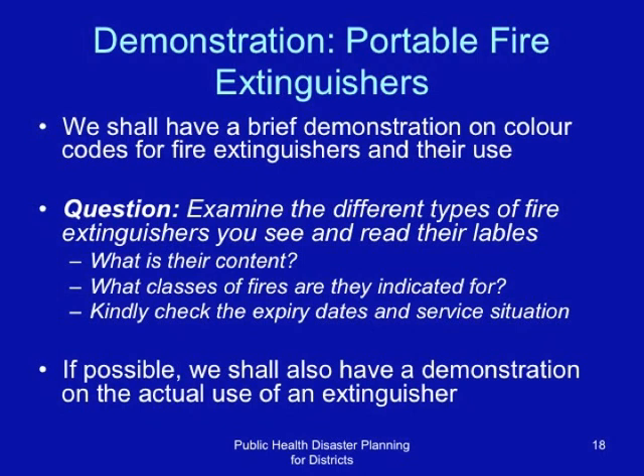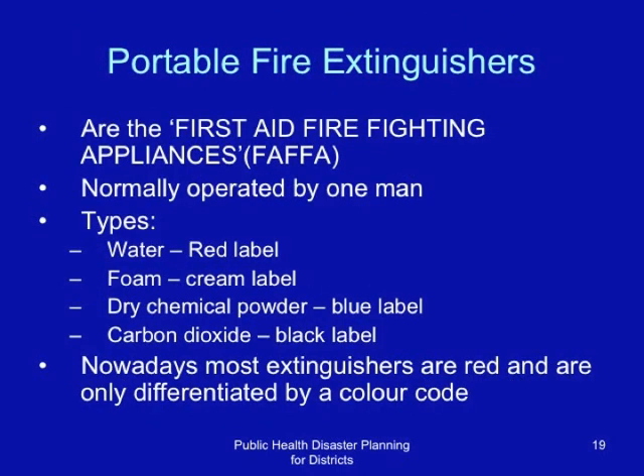Portable fire extinguishers are the first-aid firefighting equipment, FAFA, and are normally operated by one person. Water-containing extinguishers often have a red label. Foam-containing extinguishers usually have a cream label. Dry chemical powder extinguishers usually have a blue label. Carbon dioxide extinguishers usually have a black label.